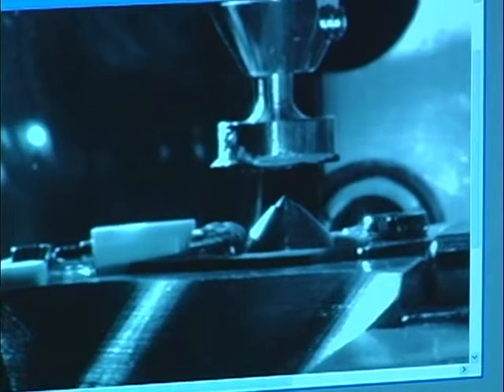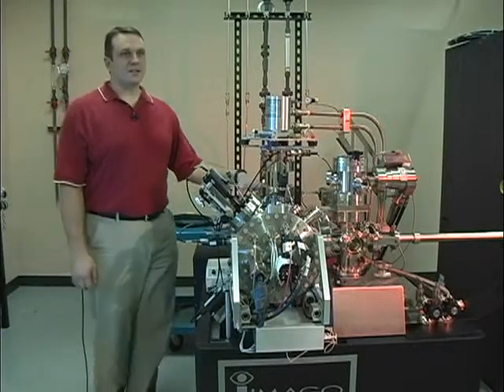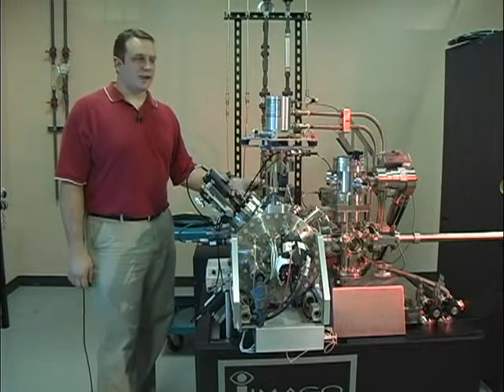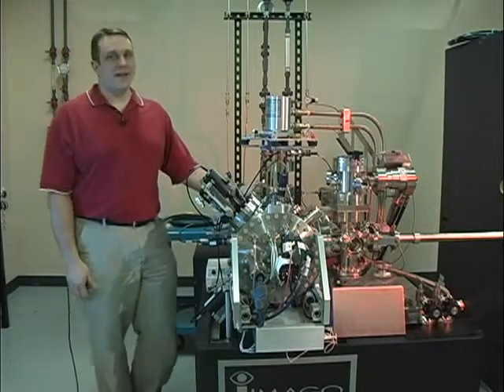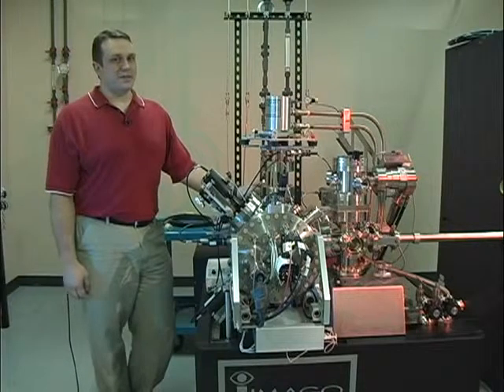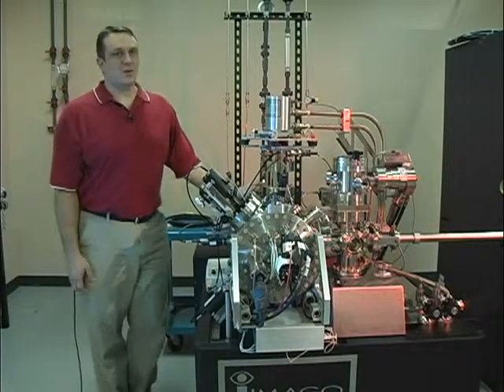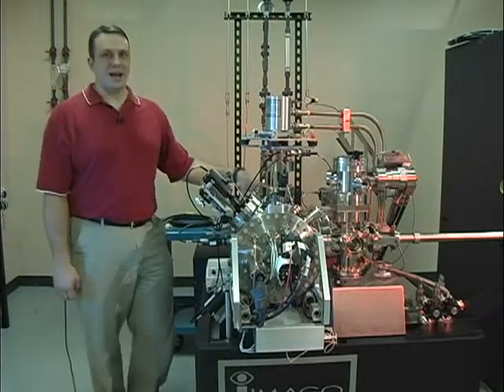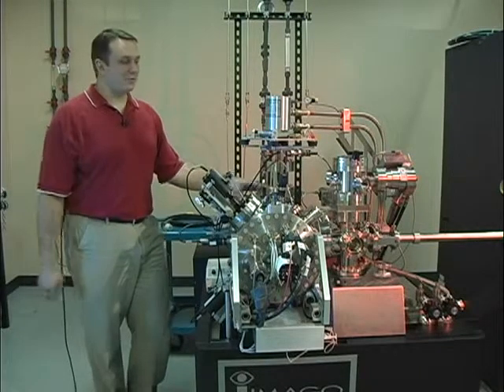Most of the components that you see on this instrument are to maintain the vacuum levels. This instrument, in order to measure individual atomic compositions, needs to run at a vacuum level 1/1000th that of space. So we're very, very interested in maintaining high vacuum, and that's what all this equipment is mainly for.